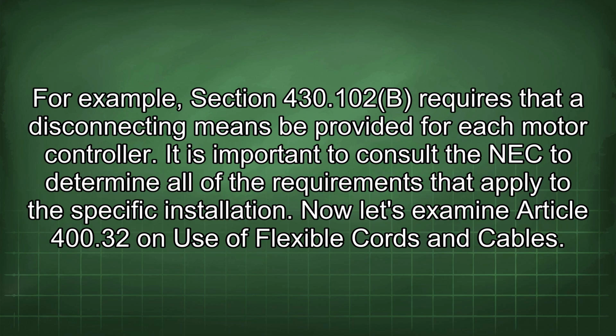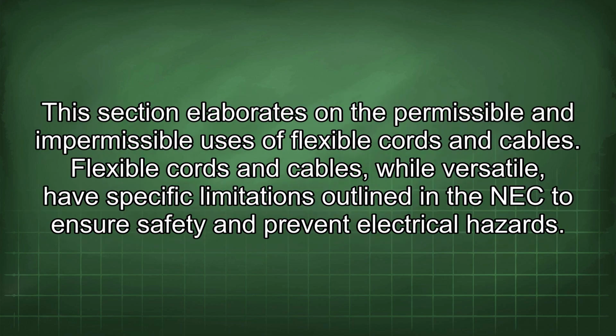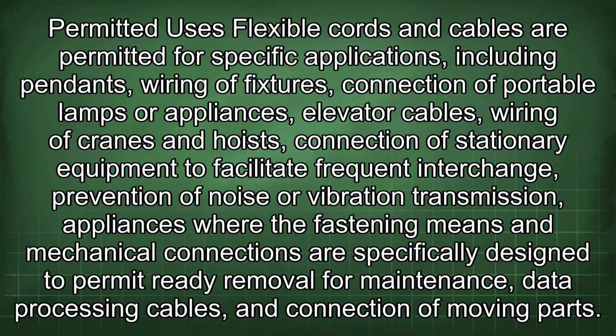Now let's examine Article 400.32 on use of flexible cords and cables. This section elaborates on the permissible and impermissible uses of flexible cords and cables. Flexible cords and cables, while versatile, have specific limitations outlined in the NEC to ensure safety and prevent electrical hazards.